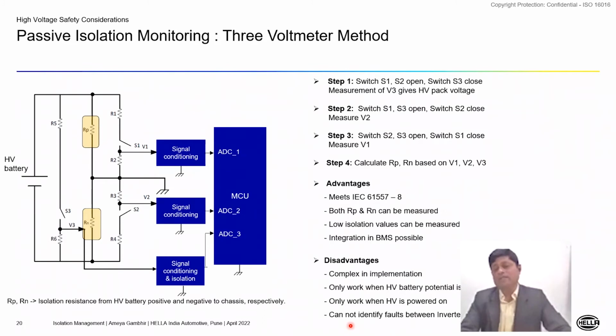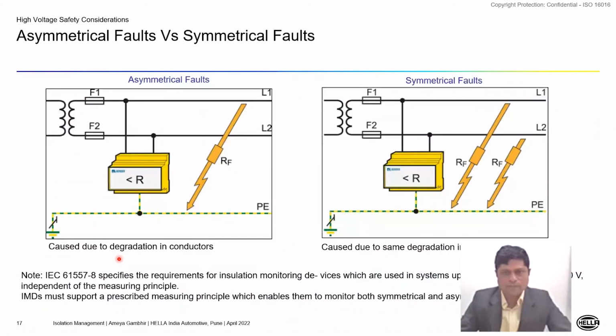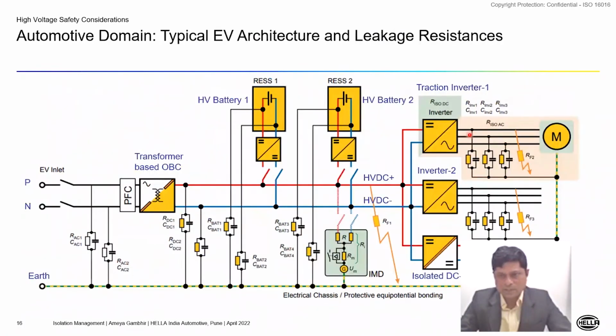It cannot identify faults between the inverter AC output and chassis. This is most commonly part of the battery management system and works with DC lines. Now imagine in our earlier diagram, if there was a fault in any of these three lines to chassis, then this passive isolation monitoring method may not help us.